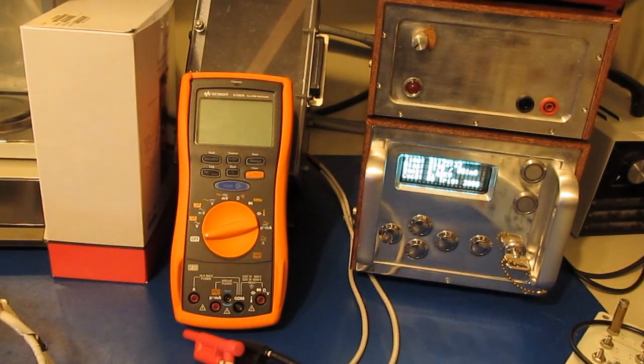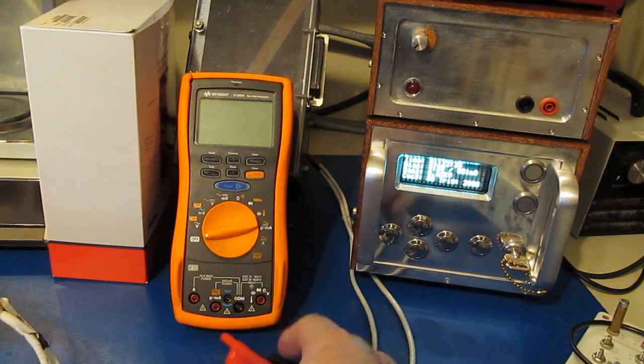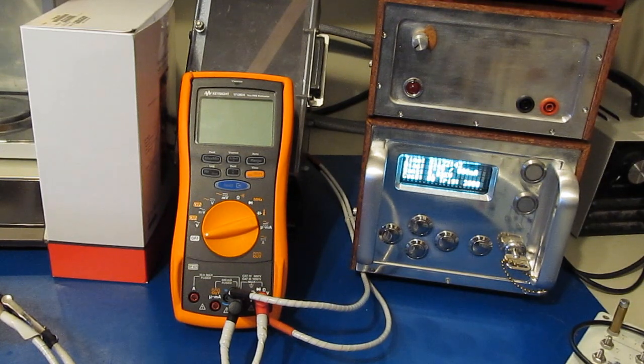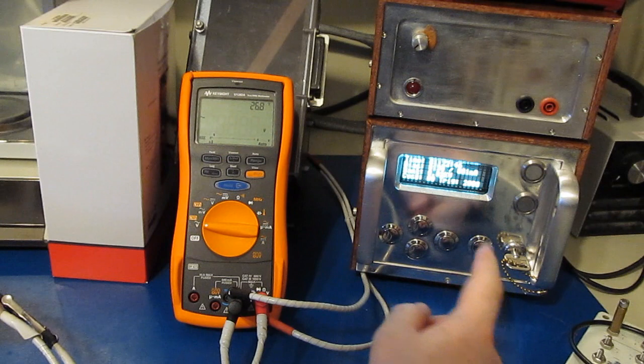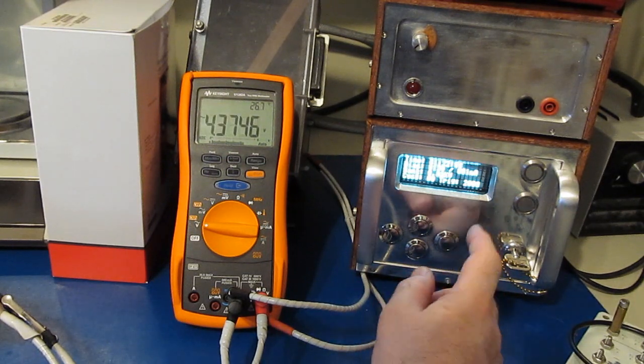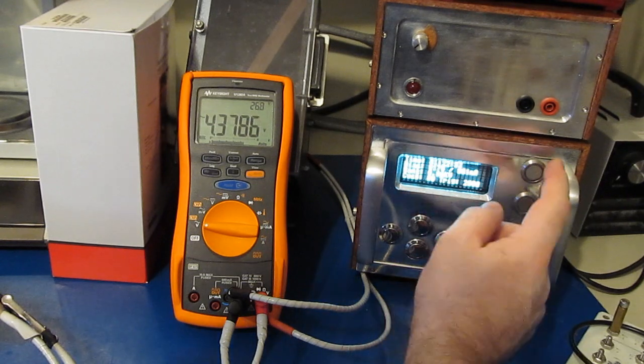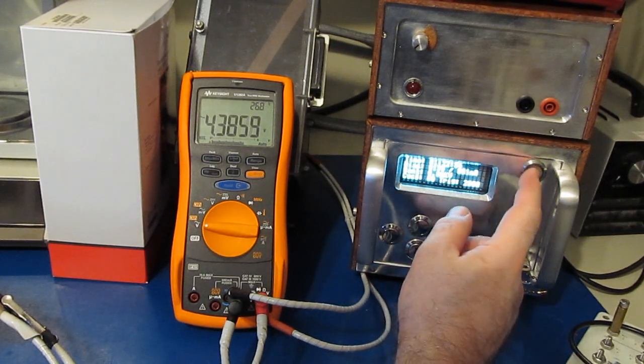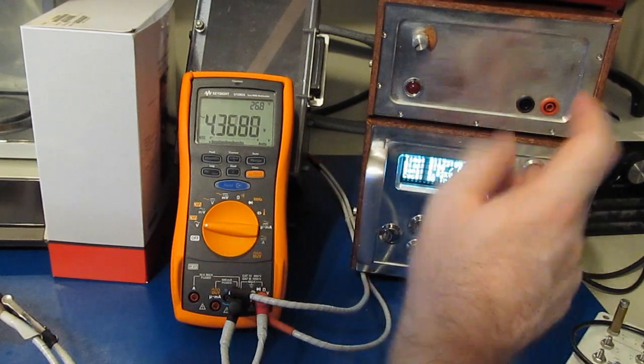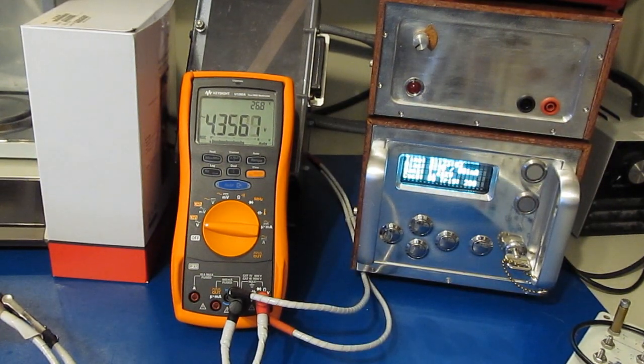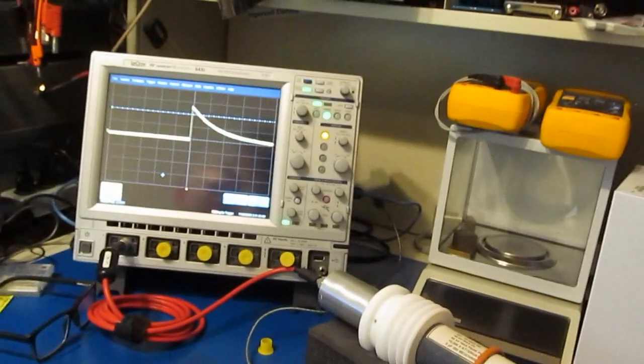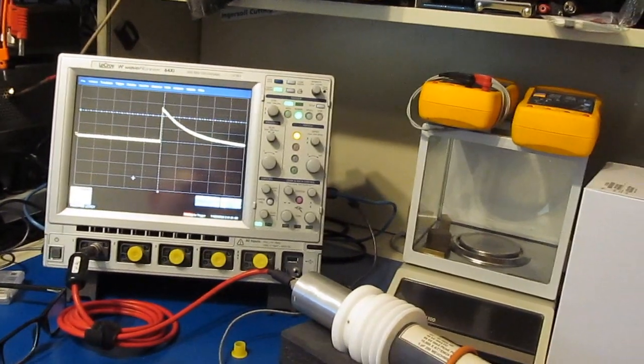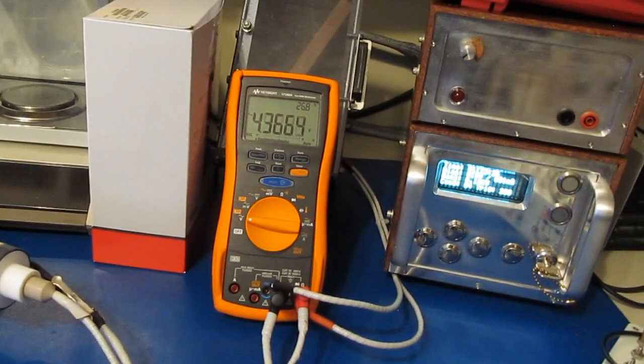Right, so the question now, with the original Keysight meter being damaged at 5,000 volts, I'm real curious to know, is that where this U1282 is going to be damaged as well? So let's give it a shot. This is going to be a 5,000 volt peak transient, a 100 microsecond full width half height, using a 2 ohm source impedance. We'll be applying 5 transients, both positive and negative, with the meter set to each mode. And no sign of a breakdown, but you can see the full width half height has shortened up quite a bit. That's because the gas discharge tubes are engaging.